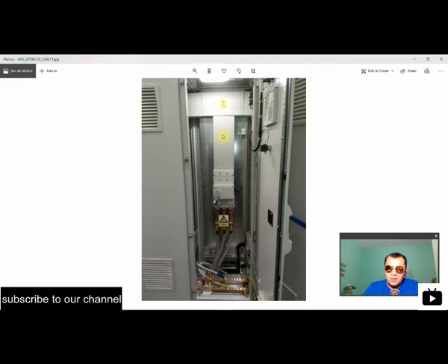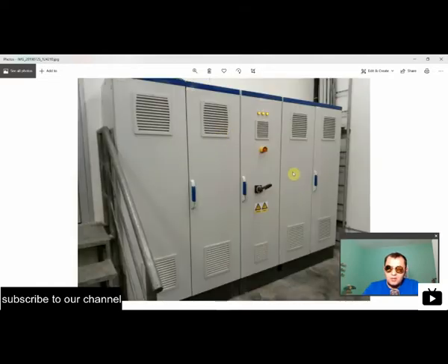As you can see over here, it's a 60 millimeter busbar system, and we are driving about 700 amperes through these busbars. This is completely possible because we used a central infeed system, so we had about 300 kilowatts in these cabinets and 100 over there, so the current is splitting to this side and to this side, and that's why on the busbars inside you don't get the maximum value of the current that the busbar can carry. In this case it was 30 times 10 millimeter busbars, and they could carry normally about 630 amperes.